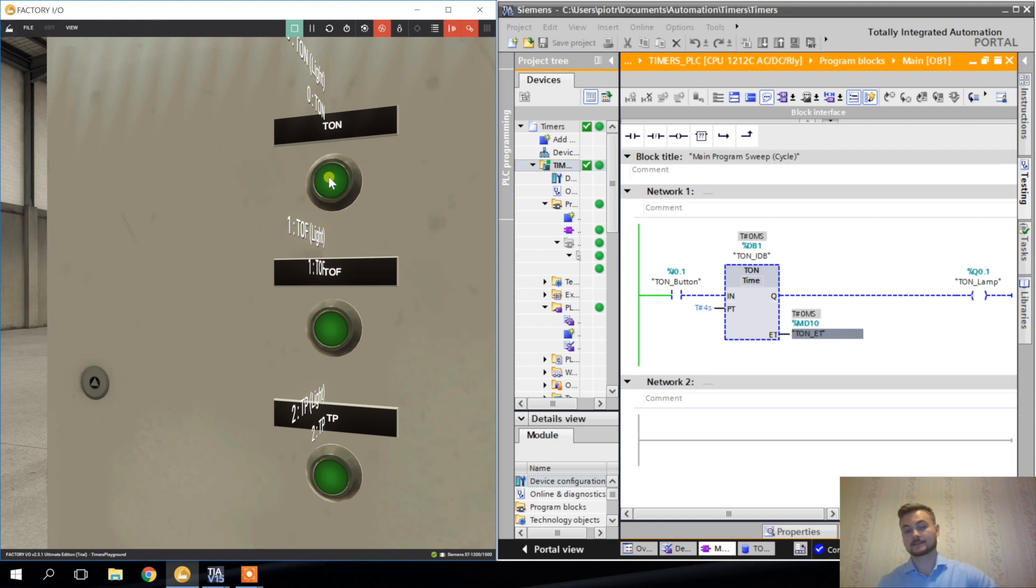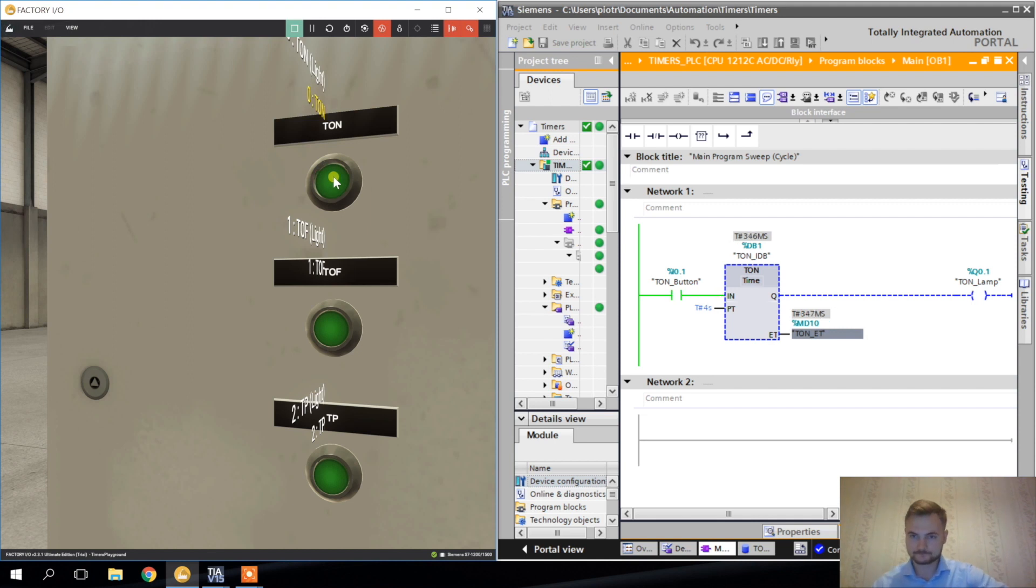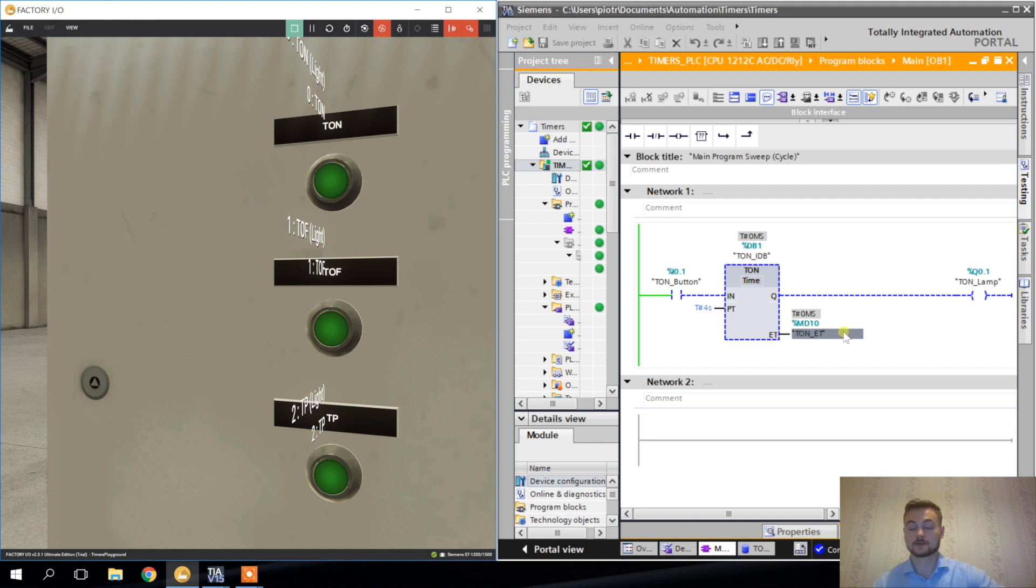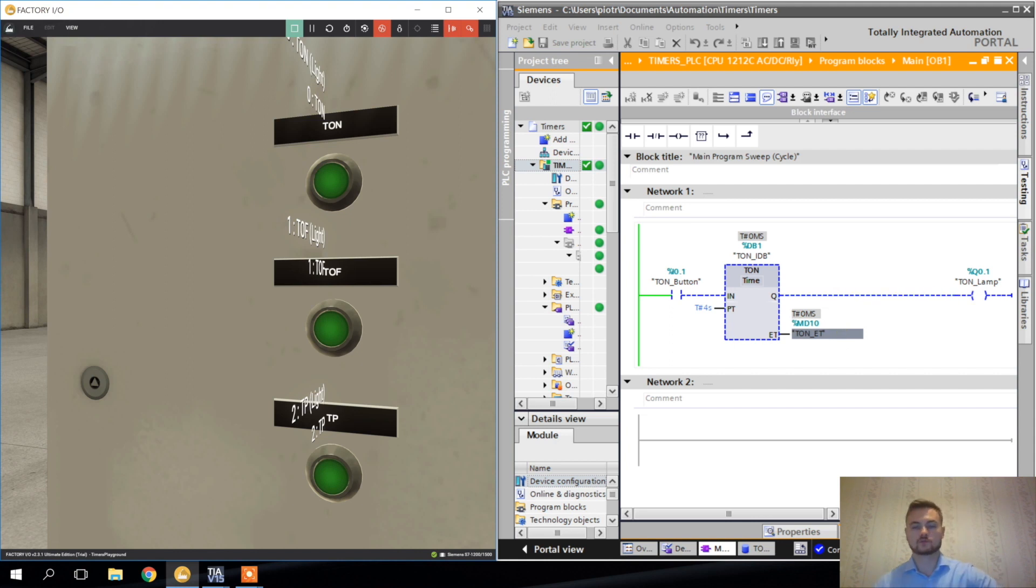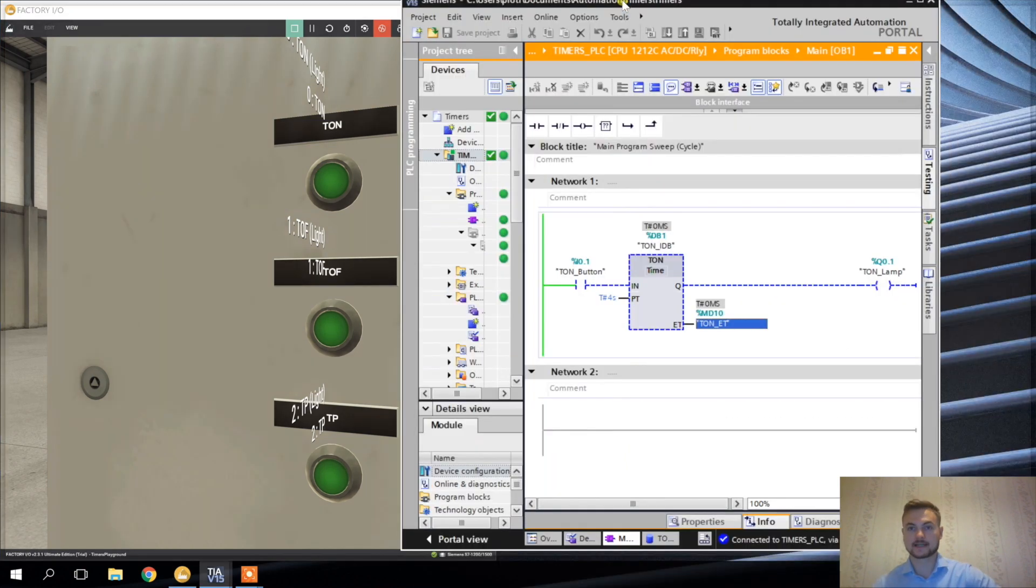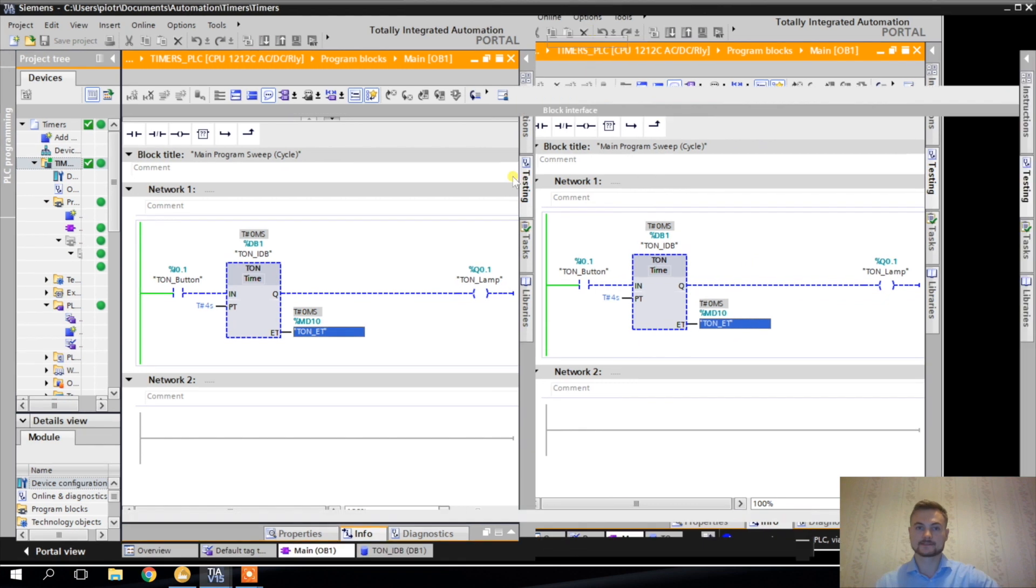I think the animation is not reacting very well. And also we don't see every scan of the PLC here. But what you can notice, this ET value rises, starts to rise after the TON button is pressed. And when it reaches four seconds, the lamp, the output Q is going on and it's lighting the lamp. Once again. And this is how it works. If I activate the TON timer for less than four seconds, nothing is going to happen. See, the ET goes to zero. So this is how the TON timer works.